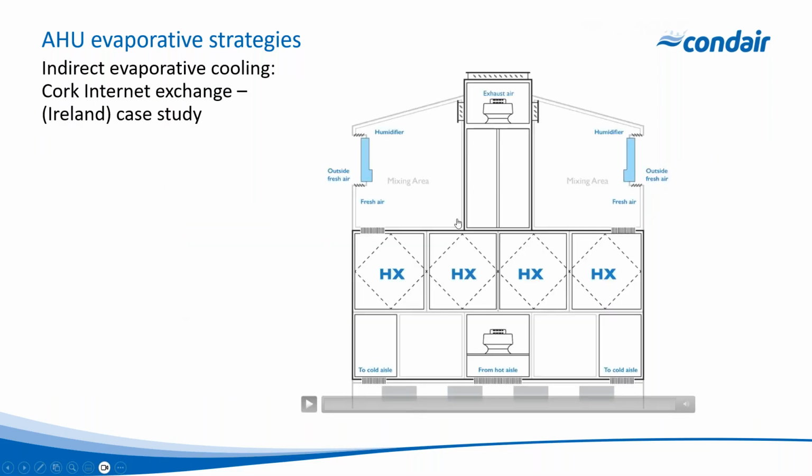So we'll go through the schematic here before we start drawing in the arrows showing the process. But this is a schematic of the air handling unit that was designed for the data hall. So we'll go through this stage by stage. So if we draw a straight line down through the unit, each side is mirrored, so the left side and the right side are both mirrored, and there are 4 circuits of airflow in the system.